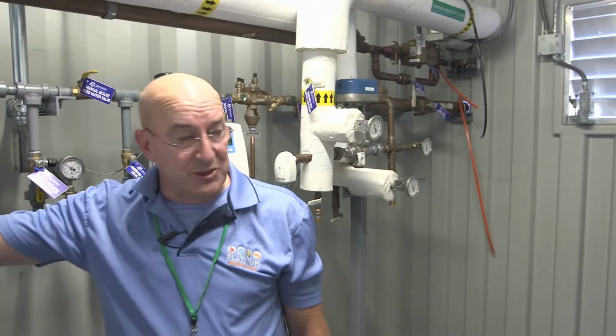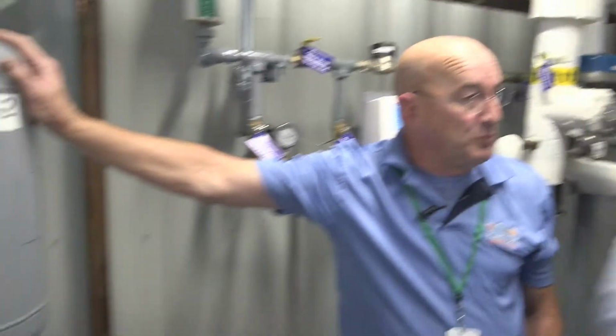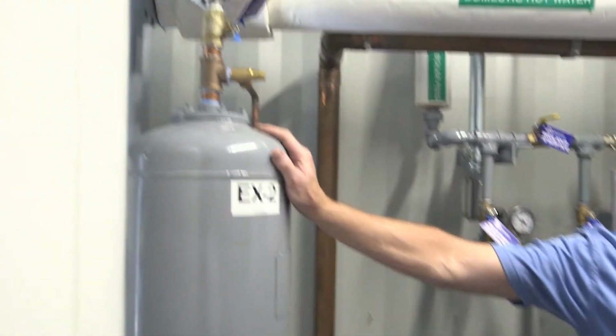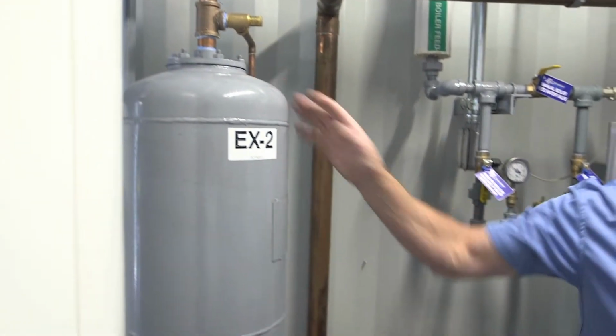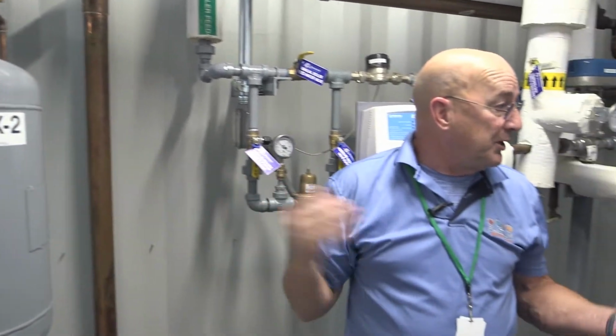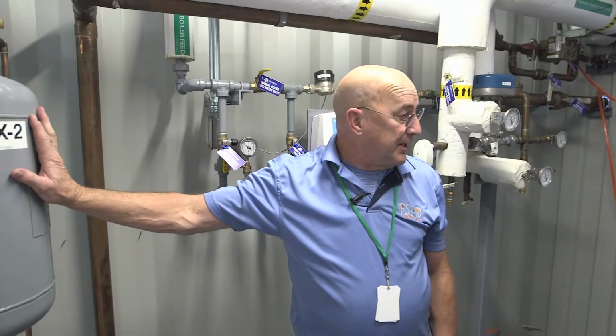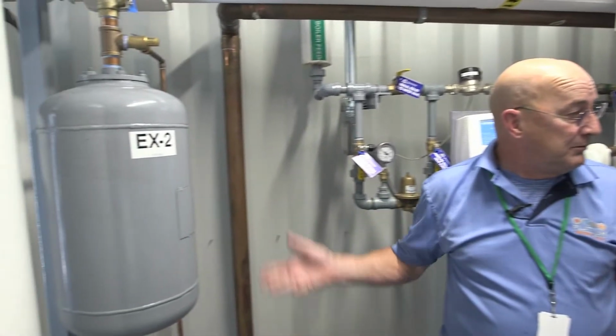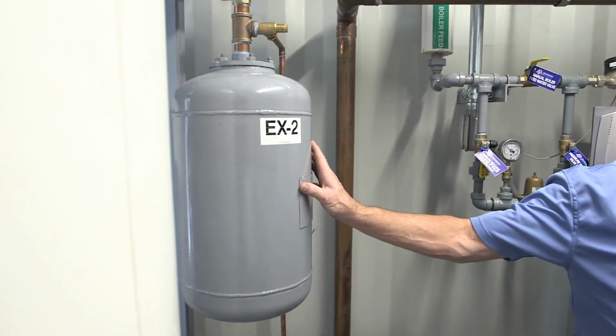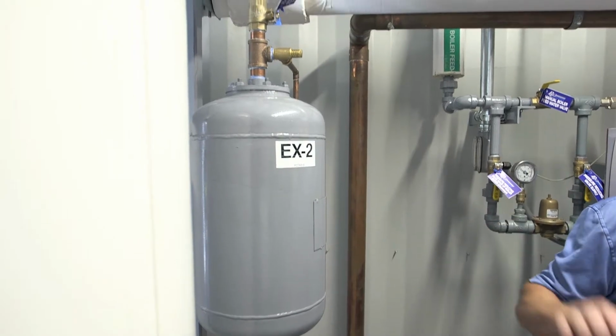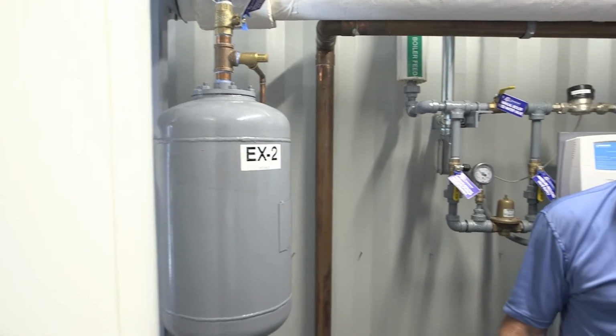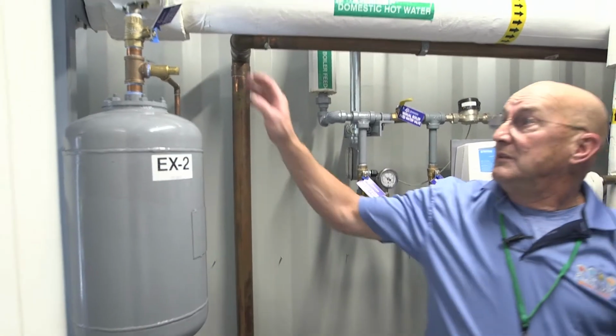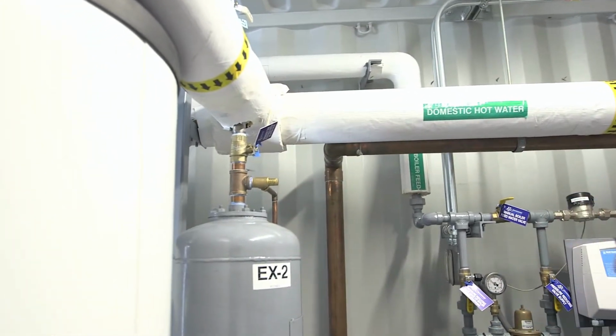This is what they call the thermal expansion tank for the domestic water. As the water heats up, you've got a check valve, so it has to have somewhere to go because it can't back up into the main. It goes into the tank. As it cools down, it pushes the water back into the system. It takes up the up and down of the pressure so that no relief valves leak. It stays on all the time. We'll move on down this way.